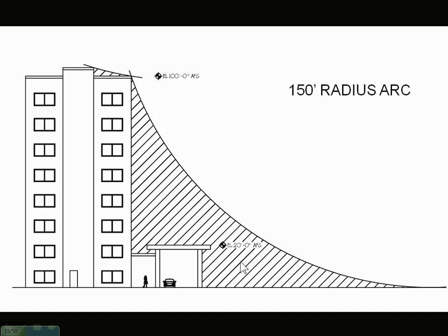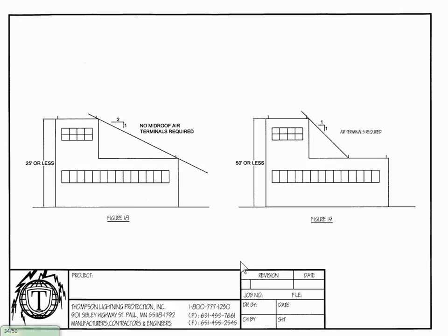And this is just a little bit easier diagram. Basically, the easiest way to calculate it: if your building is over 25 feet tall, you can use a 1-to-1 ratio. 25 feet or less, 2-to-1. So if the height of this building is 40 feet, and the height of this building is 10 feet, you can actually go out a total of 30 feet. So that's an easy way to calculate your zones of protection.